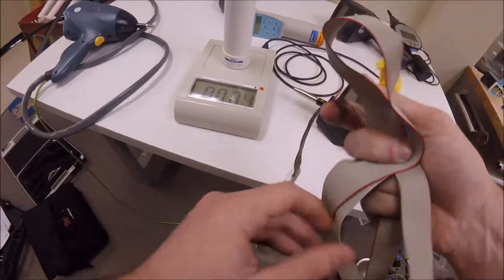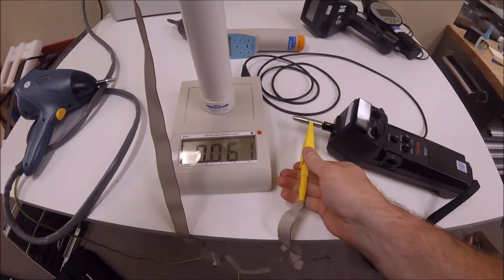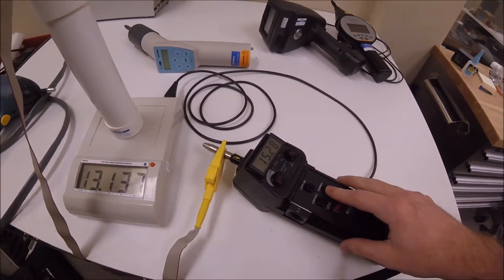Another alternative, the ESVM is supplied with a cable and alligator clip, but any cable with a 4mm banana can be plugged into the top and will connect the other end to the air tip of this here MiniZap and get consistent readings.